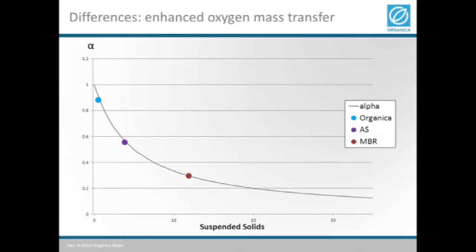The importance comes in the fact that when you blow air into the reactors, the efficiency from the bubbles of the oxygen transfer into the water depends on how clean the water is. By definition, in clean water — drinking water — that efficiency is one. This is by agreement. So the oxygen transfer coefficient is considered one when there are no suspended solids in the water. The dirtier your water becomes, the less efficient that oxygen transfer will become.